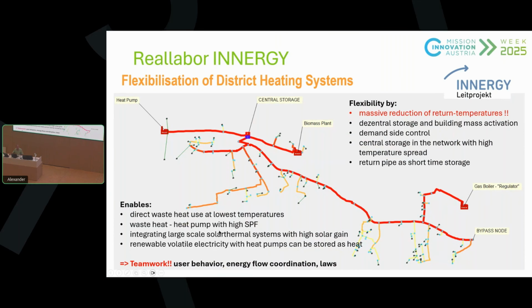Similar thing, solar thermal systems. Especially with district heating systems, I can make large solar thermal systems in Scandinavia, Denmark, Sweden, also in Germany. A lot of such examples exist, but they're again the same. If they need to produce 90, 100 degrees, efficiency is much less compared to 70 or 65 degrees. And last but not least, on the electricity side, heat pumps combined with PV or wind power, we can use and store in the network or in the storages which we have integrated in the network.